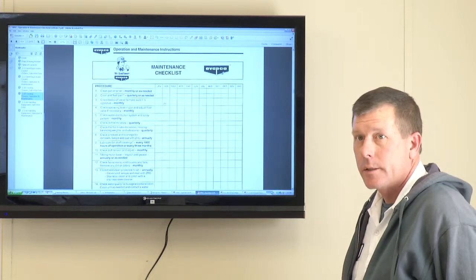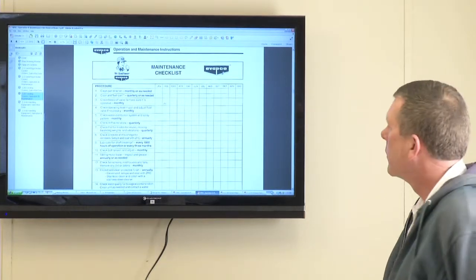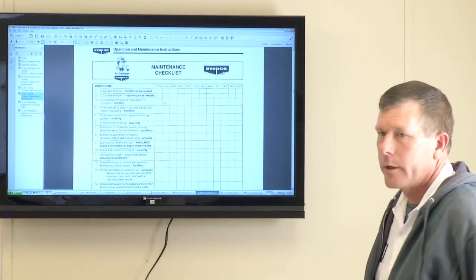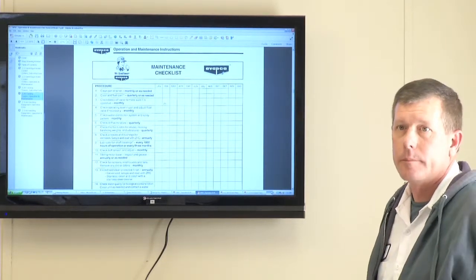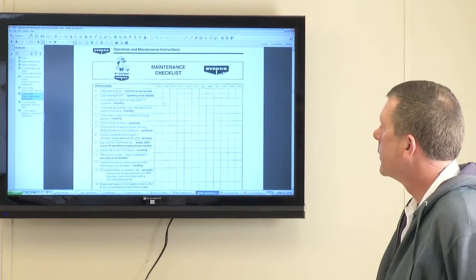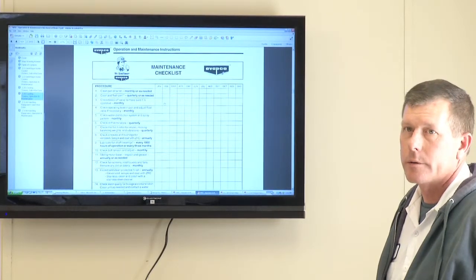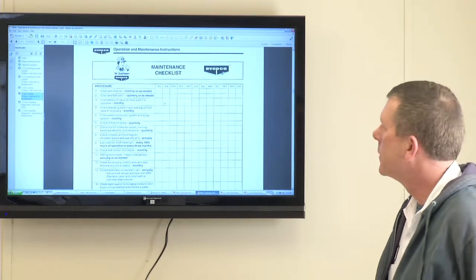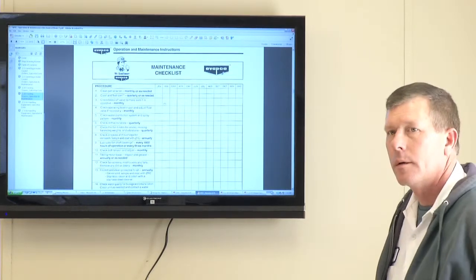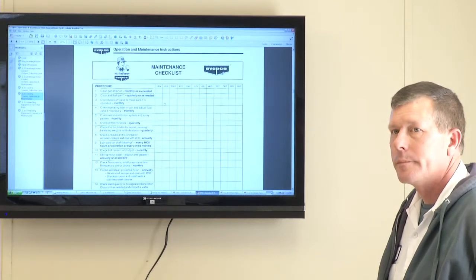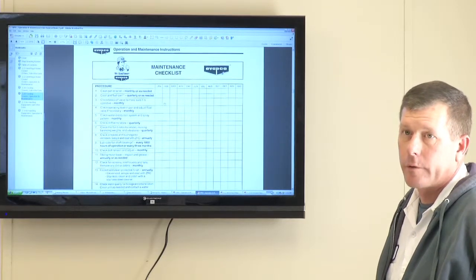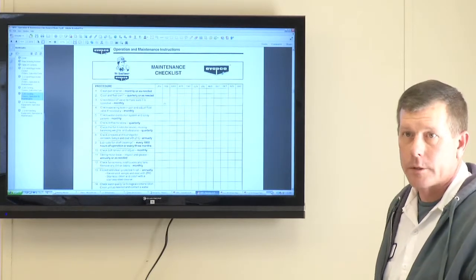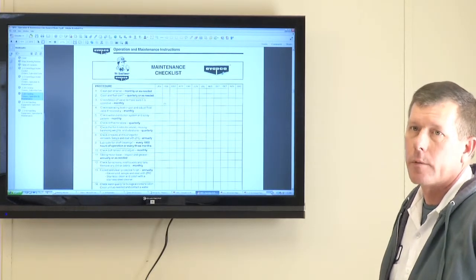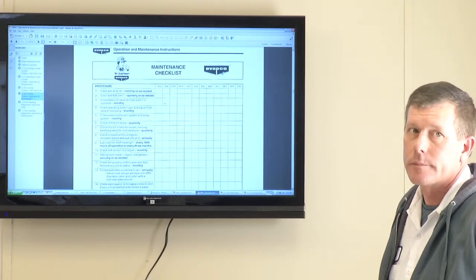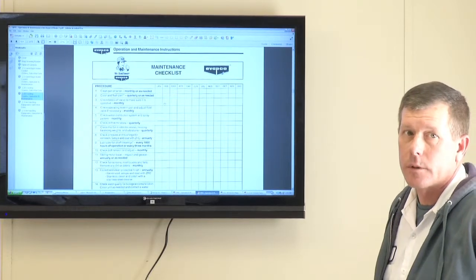Does this particular one have a one-piece belt? It's a one-piece belt on there. And all the pulleys inside of it are aluminum. And to remove those, you have to remove the drift eliminators on the top to get down in it. What about the recommended water level on the interior of the tower? Is it identified? It's right below where the overflow goes out. Of course, it takes more when it starts, then comes in where we had it, where it would keep overflowing. So right now, we are overflowing. We are? We are. Well, we'll have to check the level on the floats then.